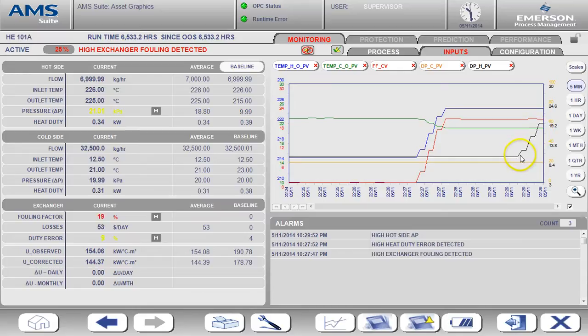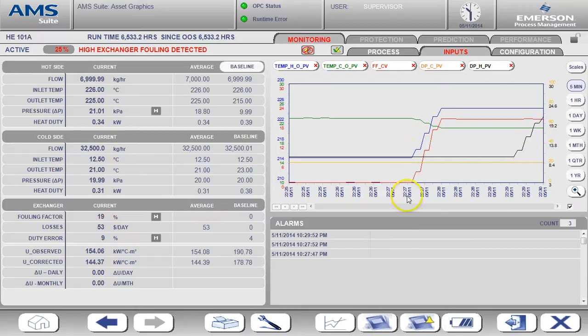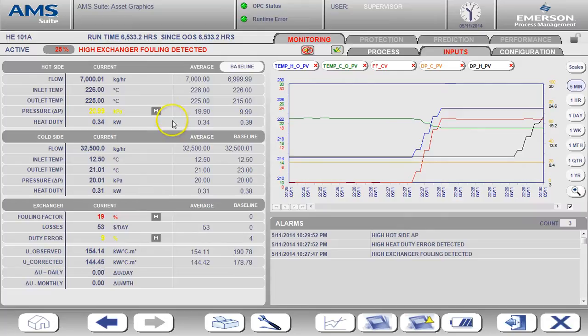You now see that the differential pressure on the hot side is high. We have the same 25% health and the same fouling alarm.